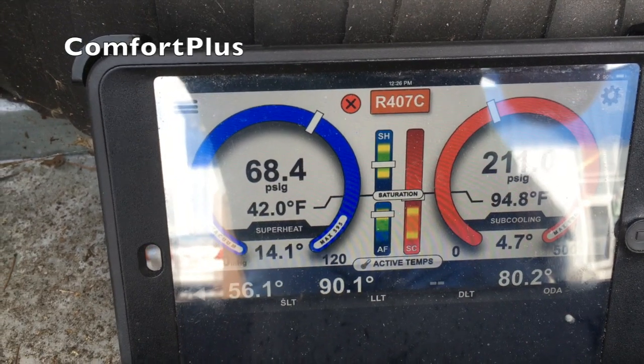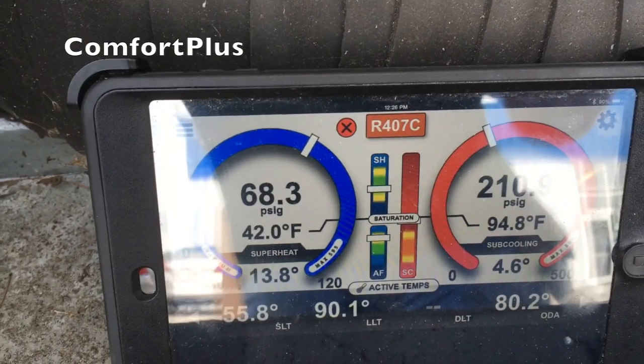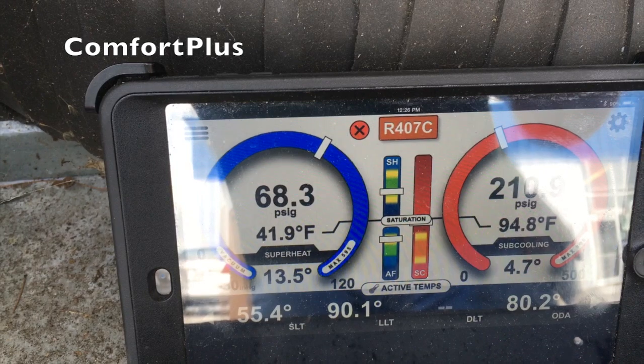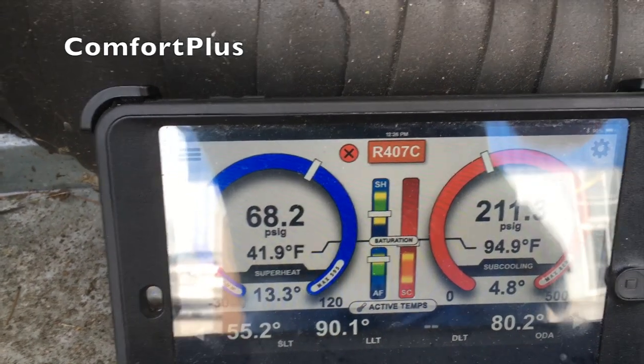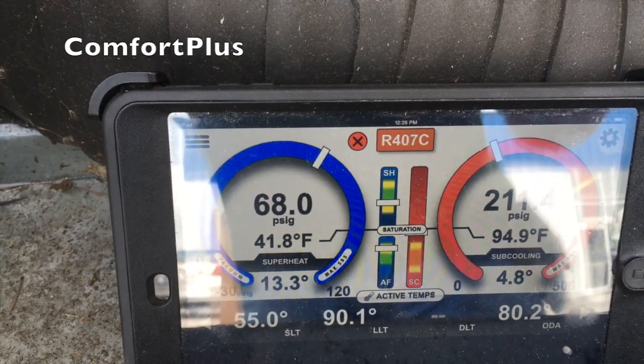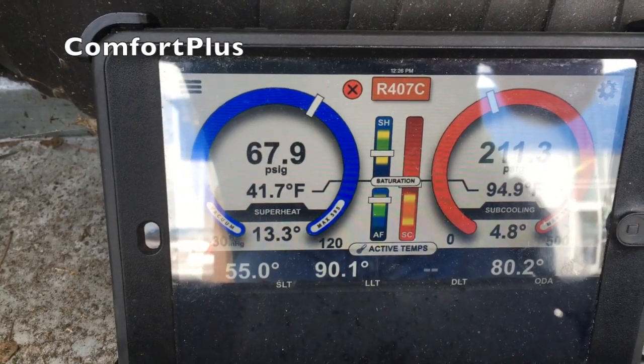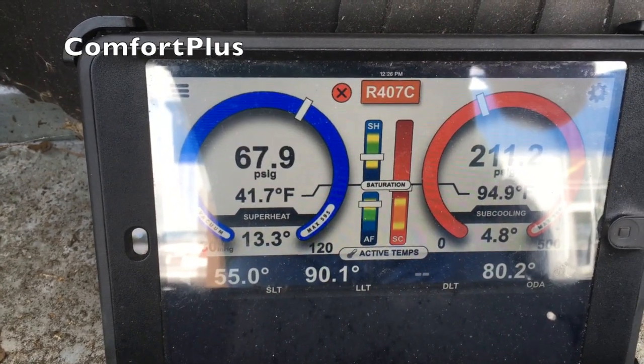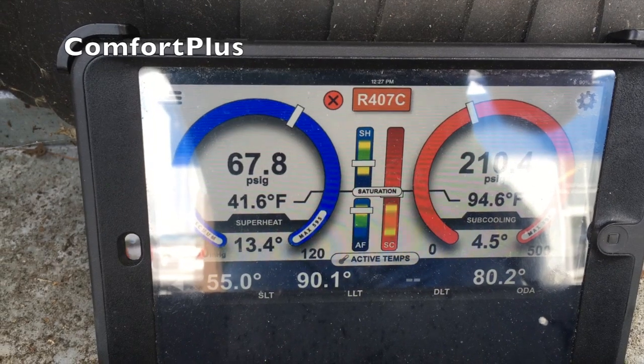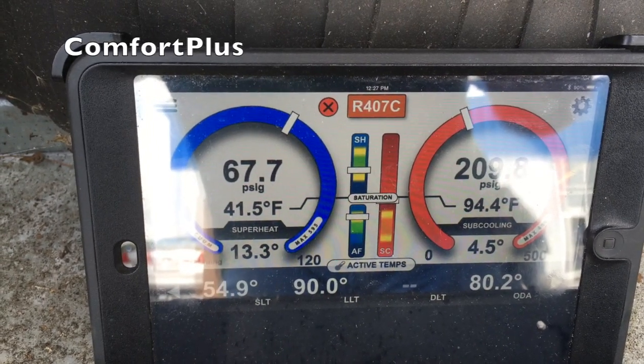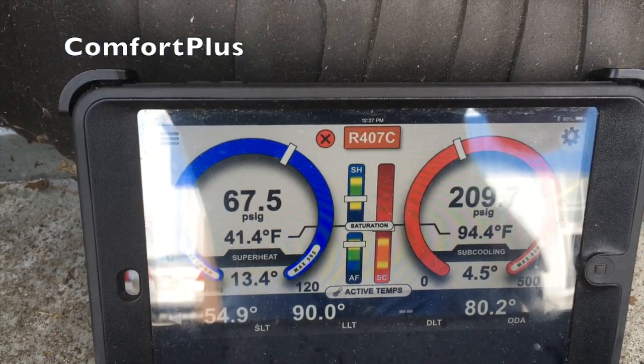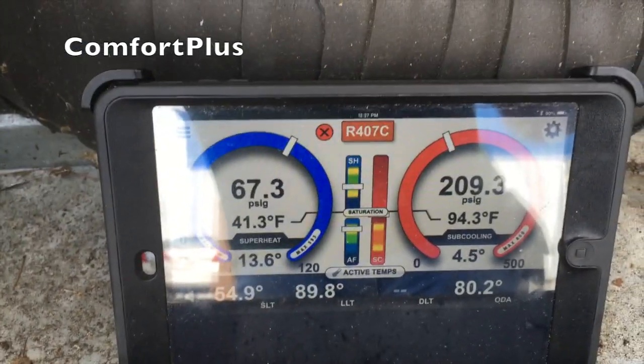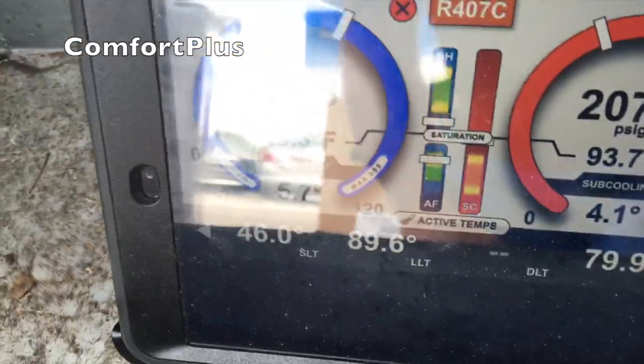The set point on this water is 50 degrees. It was 90 when we started it up, the water in the system. It's now currently about 68 and falling. And as you can see, the superheat's coming down with it. So what I want to let it do is get down close to the 50 degrees and probably set my superheat at that point. Now she's dropping like a rock. 6.1.